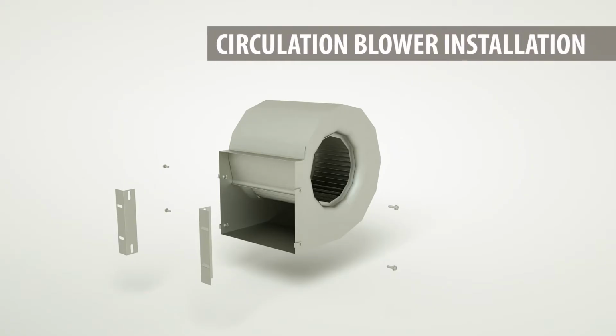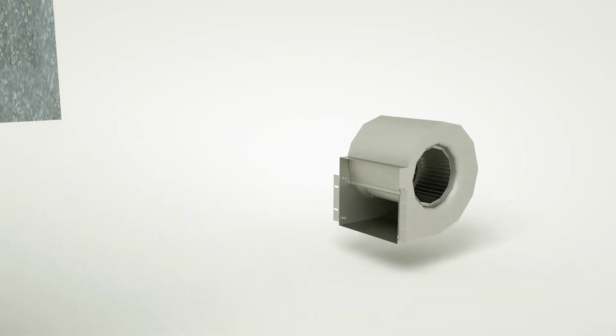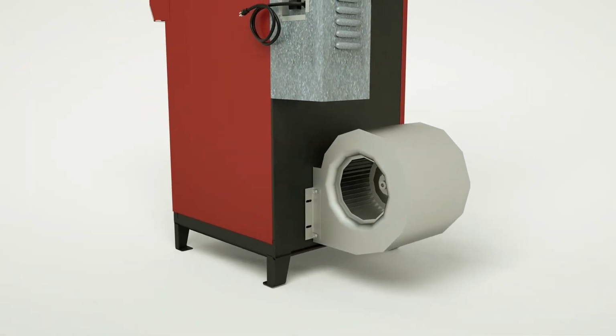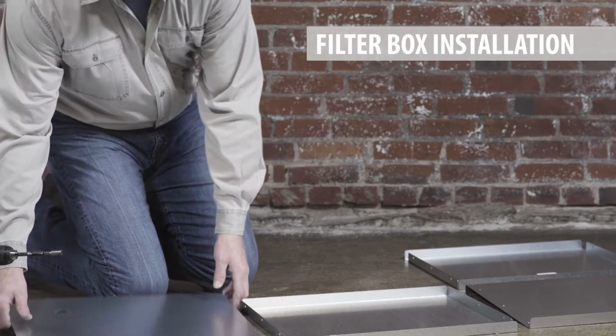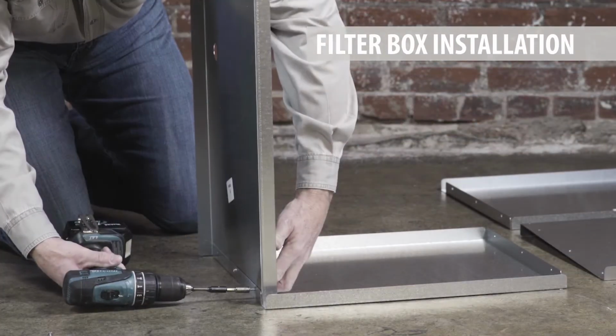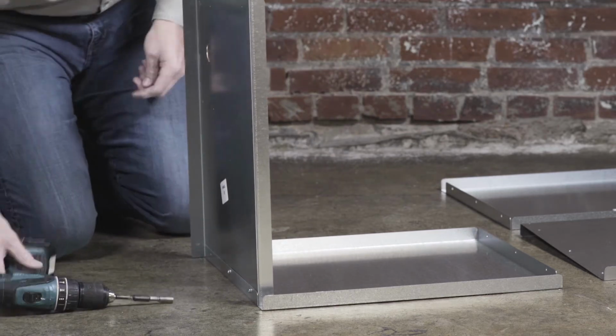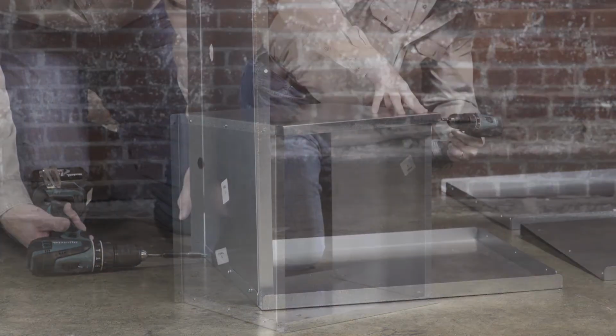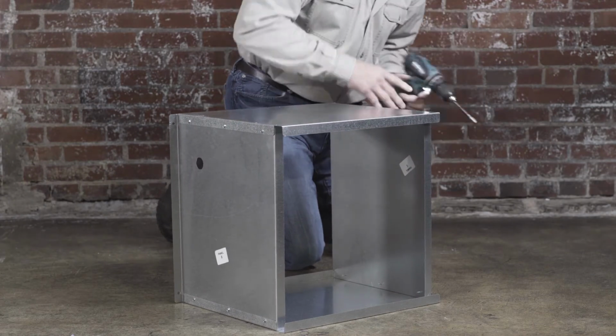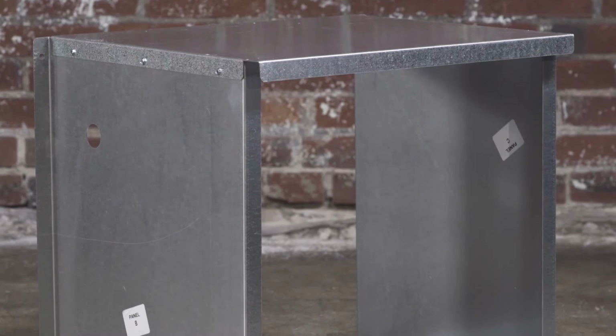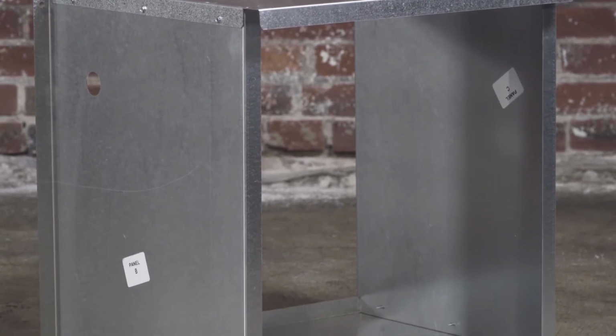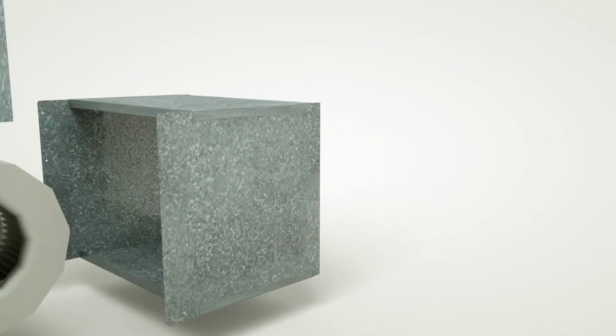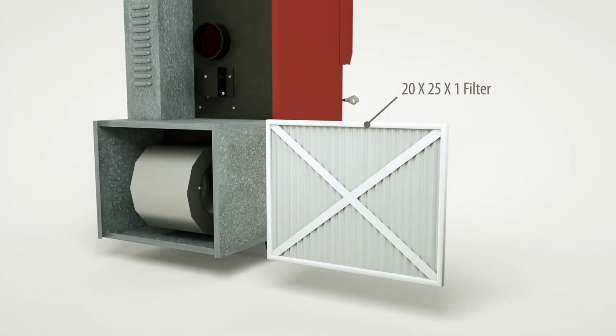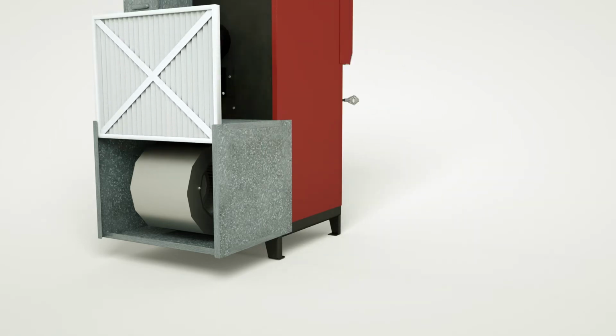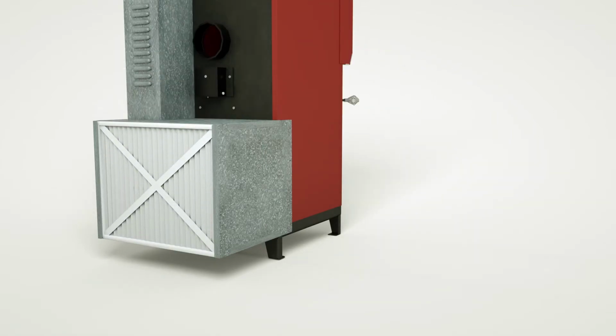The first step in installing the circulation blower is to attach the brackets to the blower housing. The blower may now be attached to the back of the furnace. You should now assemble the filter box. The filter box consists of 4 panels: a top panel, bottom panel, and 2 side panels. Be sure to identify each panel, noting the pre-drilled holes, which make assembly easy. The side panels fit inside the top and bottom panel flanges. After assembling, slide the filter box over the circulation blower and attach it to the furnace with the fasteners provided. After installation is complete, install the properly sized filter, which must be purchased separately. The filter protects the circulation blower and helps to provide clean air throughout your home.